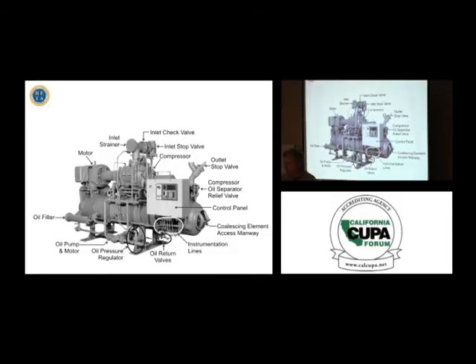So you have this everlasting rotation. Screw compressors turn fast. Traditionally, it's about 3,500 RPM. A 2-pole electric motor spins at roughly 3,600. But some designs can go up into the 4,000, 5,000 RPM range. Some will go less, especially in today's world where we're using variable frequency drives to change the capacity of the machine by actually changing its rotational speed. Point is, it's always just flowing that way, and it has a certain signature of sound and vibration.